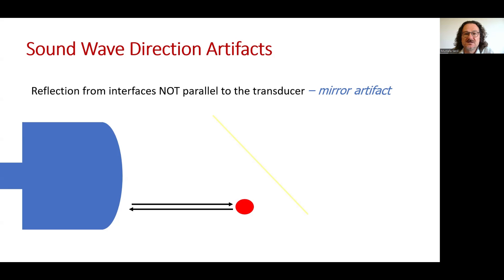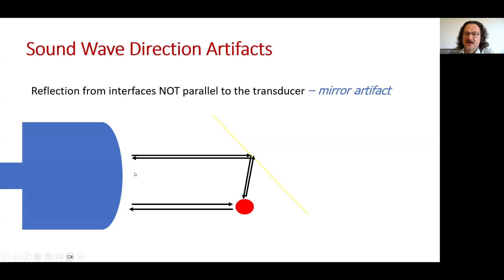Reflections from interfaces not parallel to the transducer may cause mirror artifacts. The transducer transmits and receives sound waves to obtain an image in a certain time. Some waves reflect from the non-parallel interface, reach the object, go back, reflect again, and reach the transducer. Since the transducer uses time to determine depth, the object is imaged deeper and not in its original place. This is called the mirror artifact.